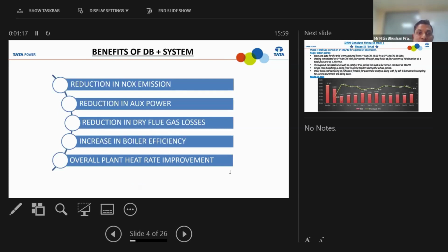This system benefits us in reduction in our NOx, reduction in our aux power, and reduction in the dry flue gas losses. As the excess air is controlled, this increases the boiler efficiency of our system, and overall there is plant heat rate improvement. As the excess air is controlled, it is able to decrease the aux power and the dry flue gases, and finally it is improving our boiler efficiency.